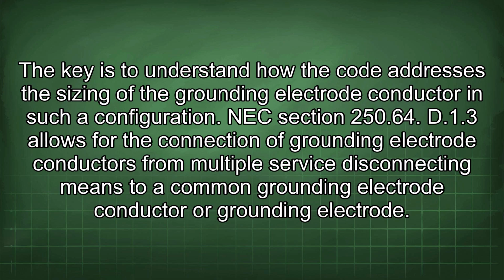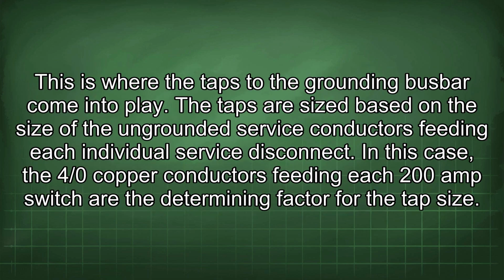NEC section 250.64(D)(1)(3) allows for the connection of grounding electrode conductors from multiple service disconnecting means to a common grounding electrode conductor or grounding electrode. This is where the taps to the grounding busbar come into play. The taps are sized based on the size of the ungrounded service conductors feeding each individual service disconnect. In this case, the 4/0 copper conductors feeding each 200 amp switch are the determining factor for the tap size.